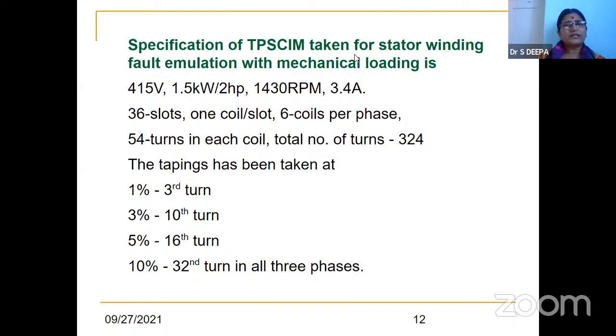So here is the specification of the three-phase squirrel cage induction motor taken for stator winding fault emulation with mechanical loading: 415 volt, 1.5 kilowatt, 2 HP, 1430 RPM, 3.4 ampere, 36 slots, 1 coil per slot, 6 coils per phase, 54 turns in each coil. Total number of turns is 324. So we have to have complete data of all the machines we work on.